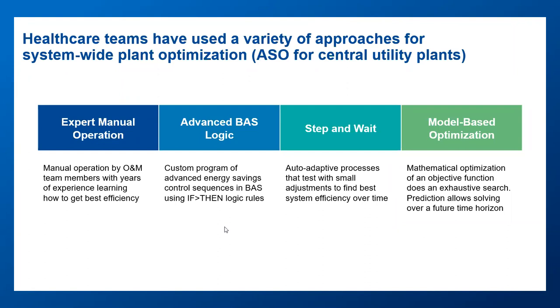The second approach is advanced logic in your plant automation system. Oftentimes these are custom programs designed by a mechanical engineering firm or programmed by an experienced controls engineer or technician directly for plant optimization. At Johnson Controls we sometimes refer to this as 'CPO Eddie,' named after one of our top programmers who used to do things this way. This approach typically has the lowest implementation cost, but it's hard to scale since there's a real dependency on the technician who built that custom program and knows it. Maintaining it over time as things in the plant change is difficult - the program often can't be very dynamic, and there isn't much learning built in. It's kind of a static set of sequence logic added to enable more advanced sequences for saving energy.